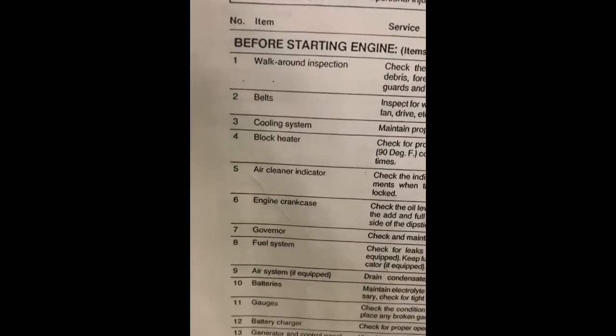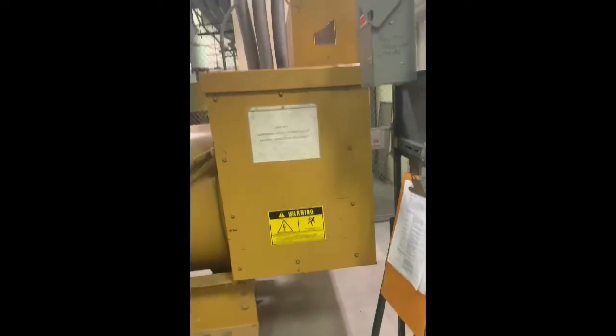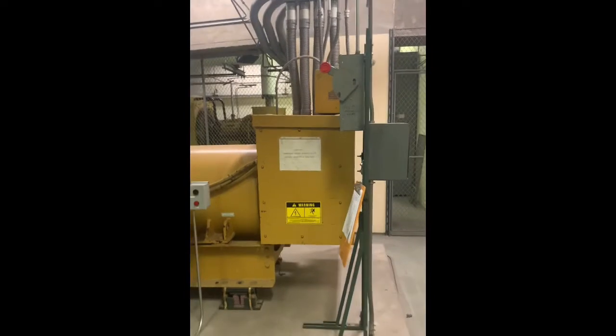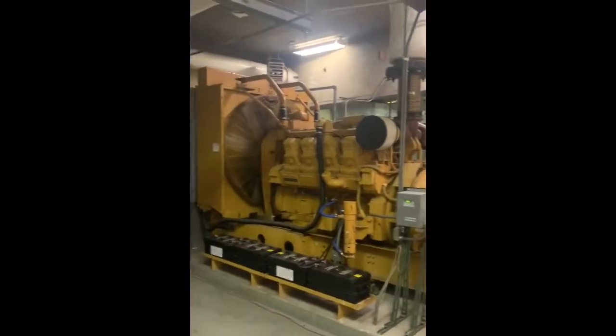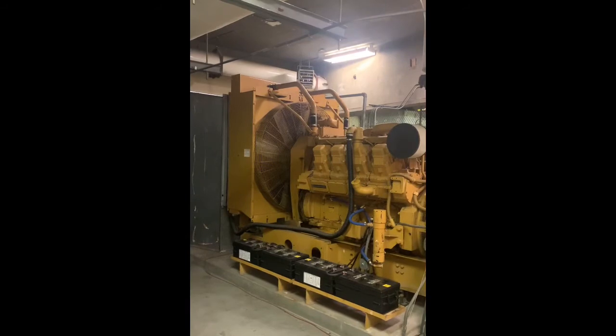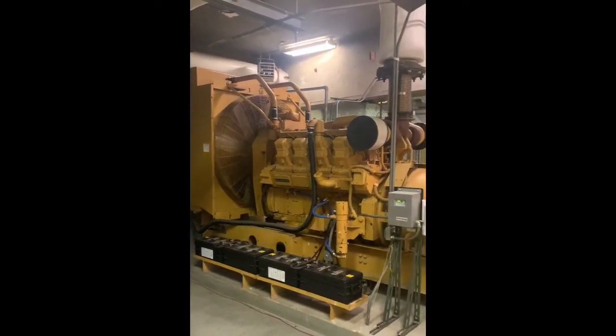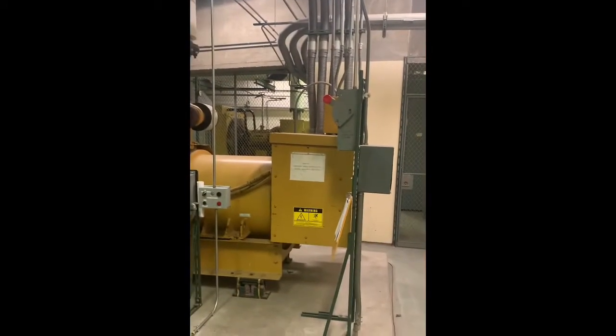One thing we like to do is once a week we'll come in here and give it a no-load test. Here's our walk-around inspection: check the belts, coolant system, block heater, air cleaner, all that stuff. We fill out the log and keep a record of it. And then annually we will have our transfer switches checked out, and we'll actually transfer a load over automatically and see how this thing picks it up, to make sure it works properly. All right, let's go into the electric room right adjacent to it.